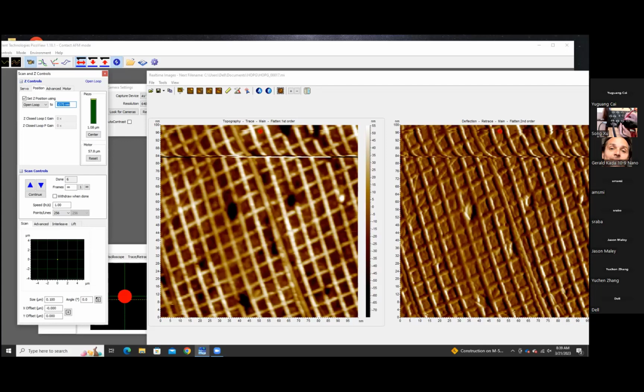Yeah, so when you move in the positive direction, you'll get a negative value. When you move in the negative direction on position, you'll get a positive value. But you're almost at 200 volts. And again, that has to do with your scanner calibration file. All I'm making sure is that your power supply turns on and moves in the proper direction with the proper amplitude. So now you can do the same thing with your servo Z position with an obnoxiously large negative value. The difference that you'll see in your measurement is it's going to be relatively the same voltage, but it's going to switch polarity. Instead of being negative 220, now you're going to see positive 220.